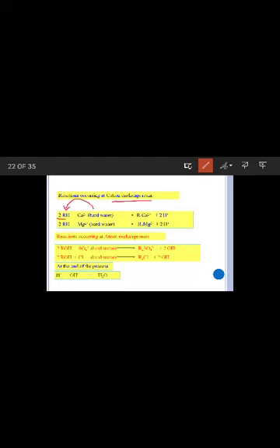There will be an exchange reaction, that is, the resin will trap the cations, so it will become R2Ca2+. So this will become resin with calcium 2+ ions, and there will be formation of 2H+. This is referred to as the cation-free water. The cation-free water is passed over the anion exchange resins.